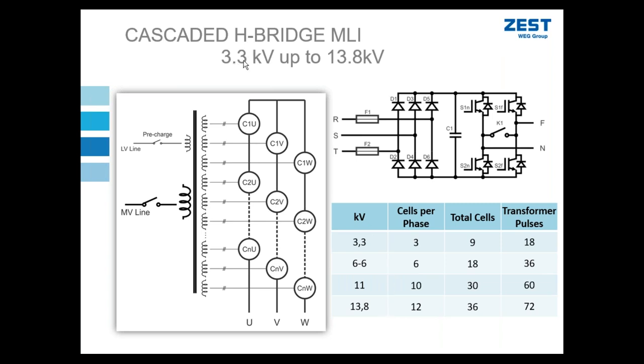As I increase my output voltage to my motor, I need to increase the number of power arms that I have in a phase. Generally, this topology makes use of low voltage IGBTs, not the 6.5 kV type IGBTs that we were discussing in the NPC topology.